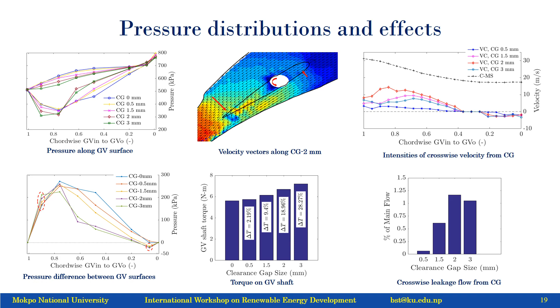I also studied the flow conditions at the runner inlet on Cu, Cm, and the relative velocity W and beta distributions. All the velocity components, Cu, Cm, W and beta, were disturbed due to the leakage flow. Strangely, we found a reduction in Cu, and reduction in Cu is actually a reduction in efficiency. We found an increase in Cm, to compensate for the decrease in Cu. So that is actually the accelerating flow.